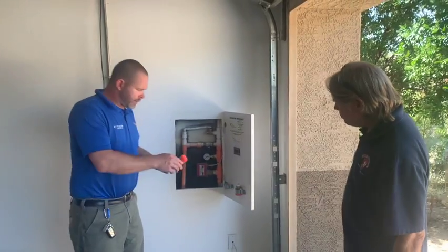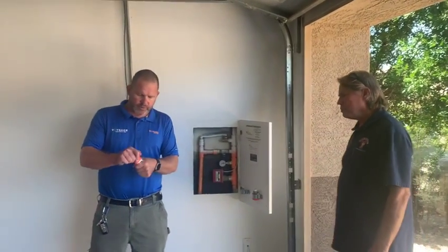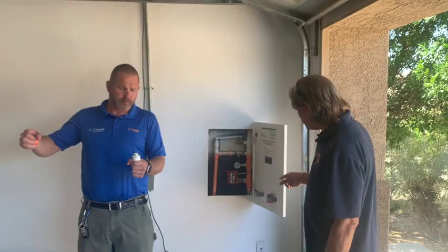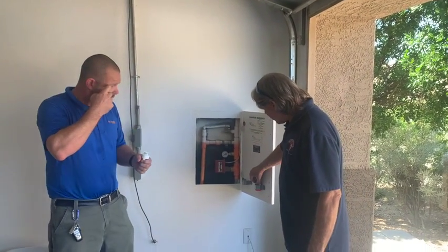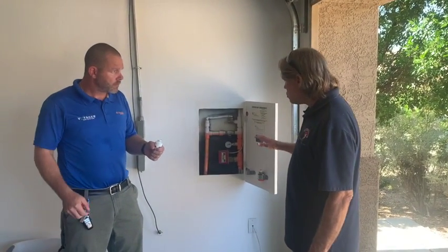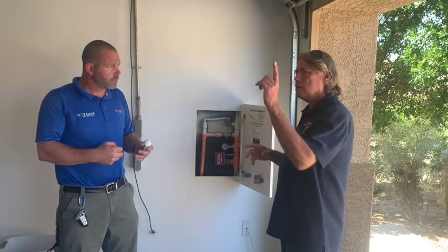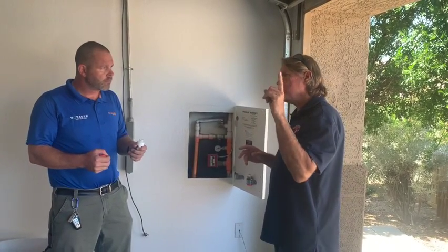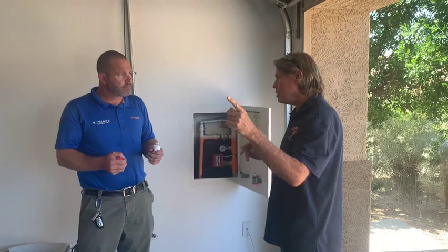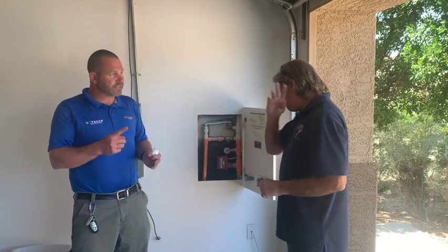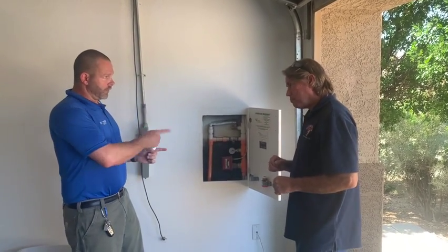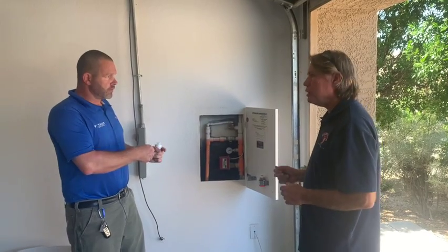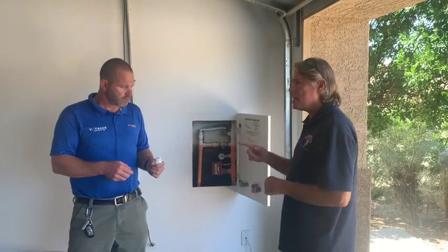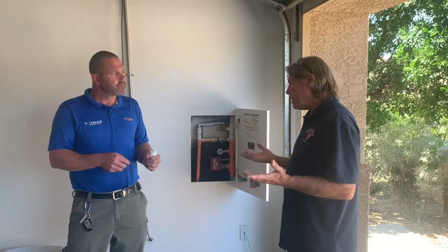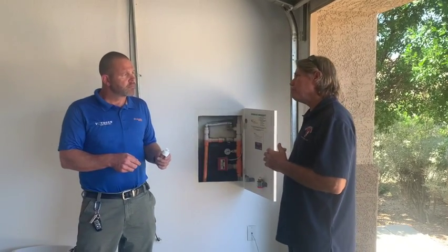Excellent. You want to run us through how fire sprinkler heads work? Sure. Now, these are spare heads. The reason these are here is by code that you have at least 2 spare sprinkler heads, one in the non-air conditioned space and one for the air conditioned space. So if you have 2 different types of heads, you should have one of each. Yeah, typically there's one of each. In this particular case, they use the same head throughout the home, and that was allowed at that time.